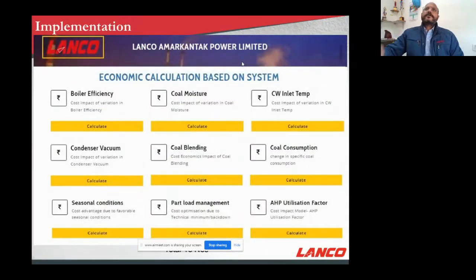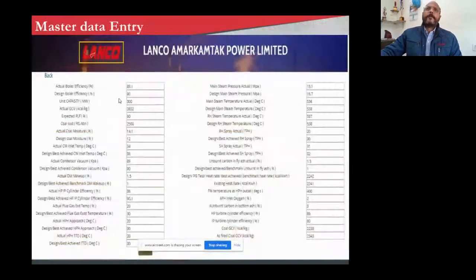This is what finally it comes up to, so we can have module-wise boiler efficiency, coal moisture, CW inlet temperature, vacuum, blending, coal consumption, seasonal condition, part load management. So one can click and then enter the respective values and get the results. Ash handling plant utilization factors. Like this, 18-20 modules are prepared. They are discrete in nature, but they are also interlinked. So if I populate some input parameters, the boiler efficiency related input parameters, they get populated into the master database, and they are available if required for other models also. Every time they don't have to fill it up. So like this. Alternatively, there will be a master datasheet entry. You enter all the values there.